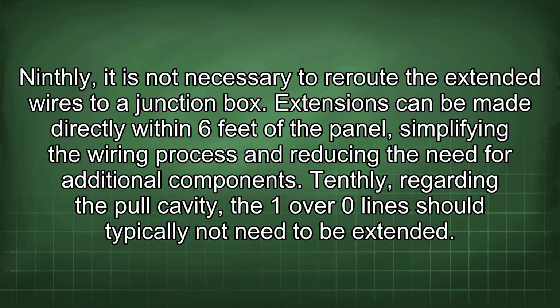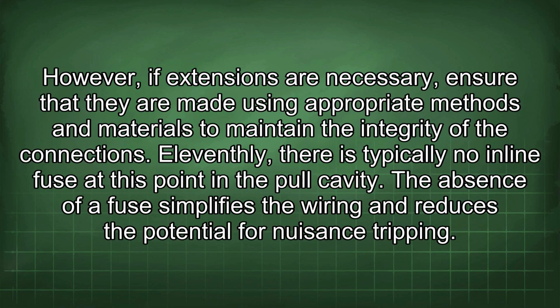Tenthly, regarding the pull cavity, the 1/0 line should typically not need to be extended. However, if extensions are necessary, ensure that they are made using appropriate methods and materials to maintain the integrity of the connections. 11thly, there is typically no inline fuse at this point in the pull cavity. The absence of a fuse simplifies the wiring and reduces the potential for nuisance tripping.